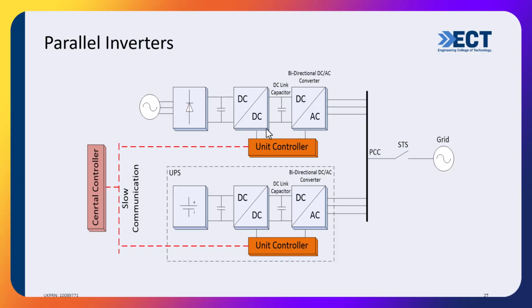So here we have the unit controller that manages the primary control level to generate PWM and calculate the power and manage the droop control. It decides how much power we need to give to the grid, and the other unit decides how much power it needs to give to the grid, or how much power to draw from the grid to charge its battery. We also have central control with slow communication, meaning I don't use it for managing power between them, only for monitoring.